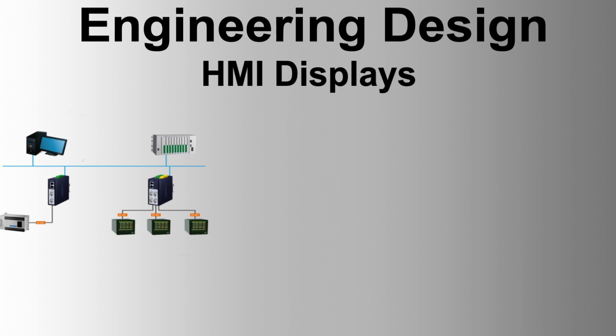Alarm presentation, graphic configuration. Alarm information should be presented in a user-friendly manner, with clear descriptors and visual indicators of alarm status. Representative alarming and dedicated graphic pages for alarm suppression can enhance alarm management. Audible alarm. Different audible tones can be configured for alarm priority levels. High-priority alarms should have a continuous tone, while medium and low-priority alarms should have an intermittent tone. The volume should be adjustable above the control room background noise level.